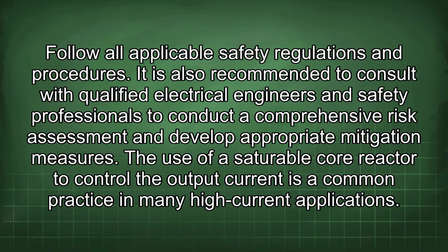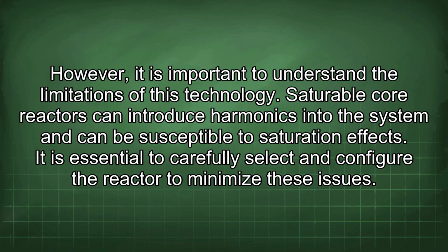The use of a saturable core reactor to control the output current is a common practice in many high current applications. However, it is important to understand the limitations of this technology. Saturable core reactors can introduce harmonics into the system and can be susceptible to saturation effects. It is essential to carefully select and configure the reactor to minimize these issues.